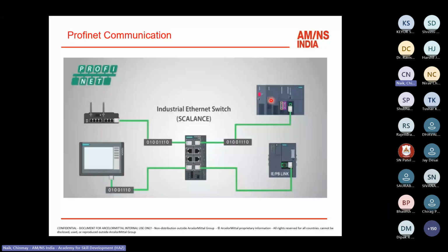This switch you might have seen in some data server. The same sort of switch is used in an industrial environment also. These switches are helpful to communicate with PLC, DCS, and other smart devices, or even relays. It's a combination of all devices connected with this switch, which we call an Ethernet switch. Normally this Ethernet switch is used for IT networking, but it is also used for industrial data networking, and that is called operational technology. So when it comes to industry, there are two terms: one is IT and the other is OT. Operational technology data is very, very important data, and it is communicated separately from the IT data.